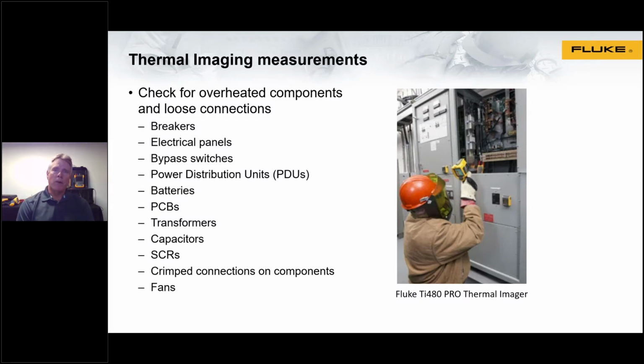One of the ways I like to look at thermal imaging when it comes to UPS systems is really more as a screening tool to be able to highlight potential problems that could cause issues, manifest different types of symptoms. So it's an excellent screening tool. Infrared cameras are fast, they're non-invasive, and you can see a potential problem, and then based on what the image is telling you, then you can take action.